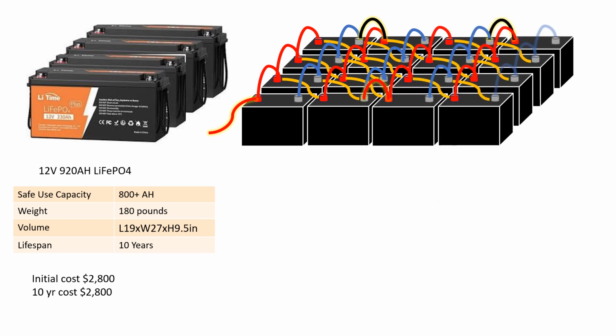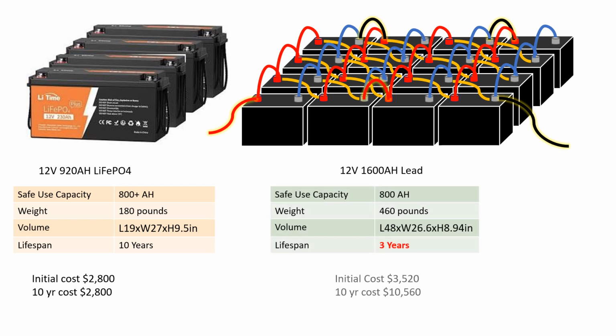So now we're talking 16 6-volt batteries wired in parallel and series to get up to a 12-volt, 1600 amp hour lead bank. That gives us a safe use capacity of 800 amp hours at a whopping 460 pounds. We've got well over double the footprint, and the cost here is over $10,000. So lead really isn't cheaper in the long run.